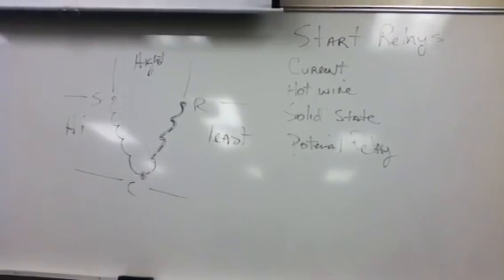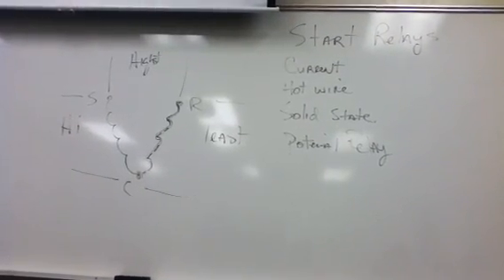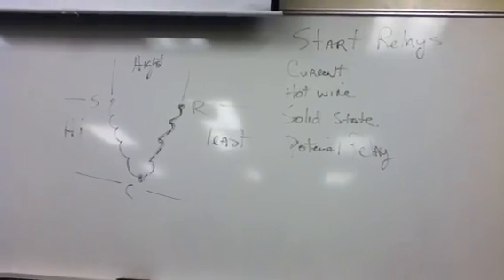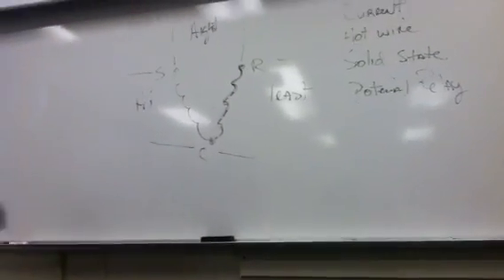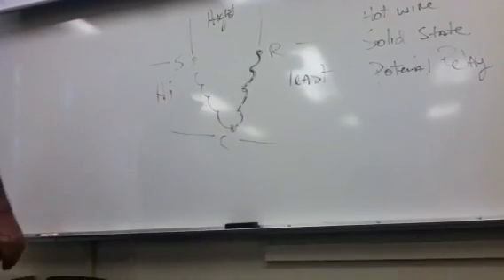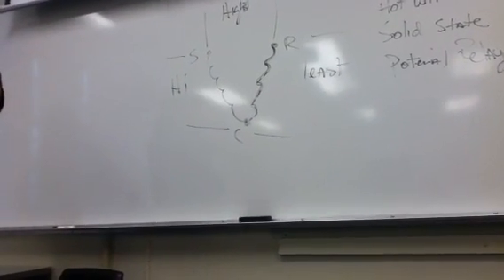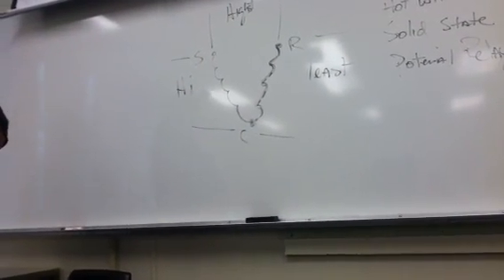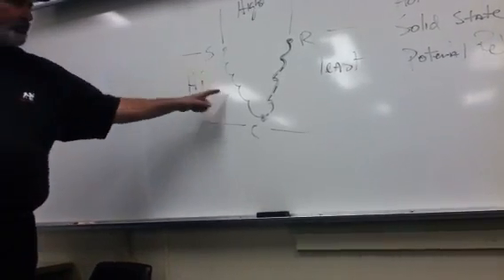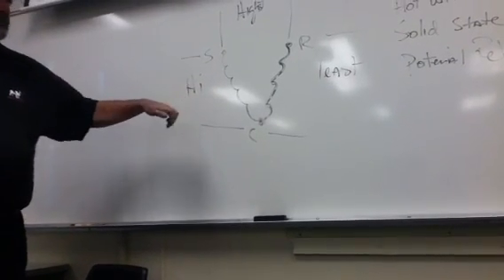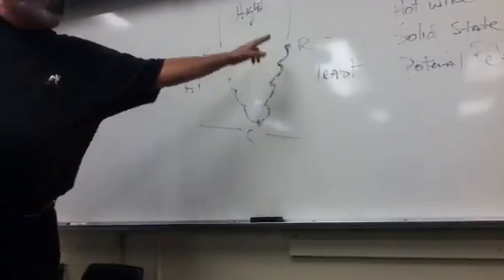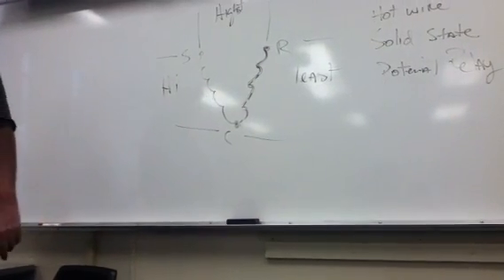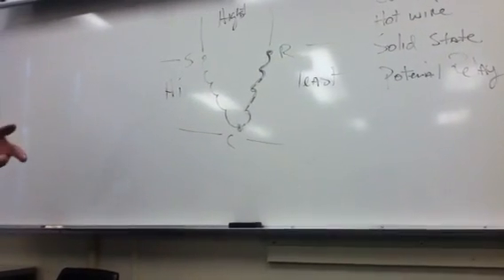Now, I'm not going to talk about how to ohm out a compressor today. I just want to explain to you the difference. There is a difference. The start winding is the winding that's physically closer to the stator. You hold the motor up and you look at it and you can see the wire is thinner. Because the wire is thinner, it has a higher resistance than the run winding which has a thicker wire. The highest reading is through both.